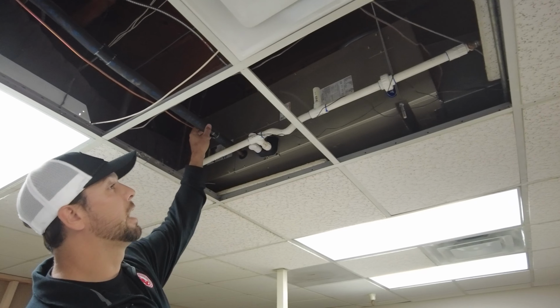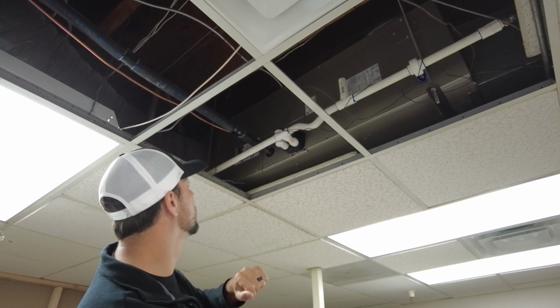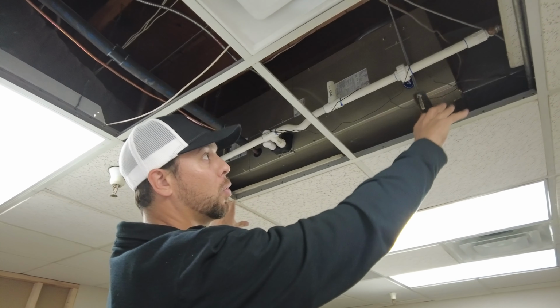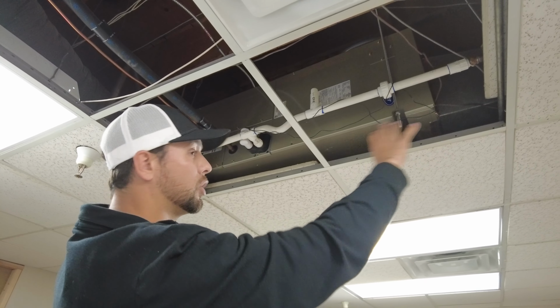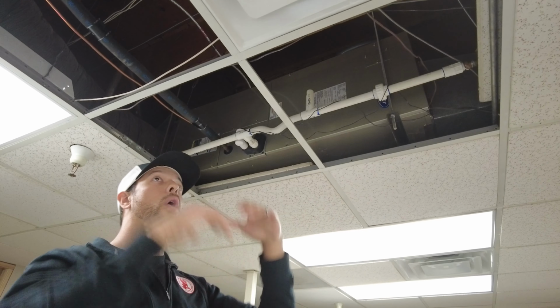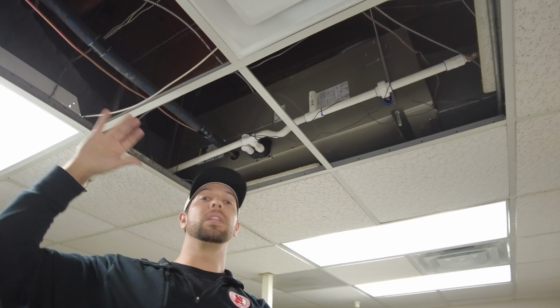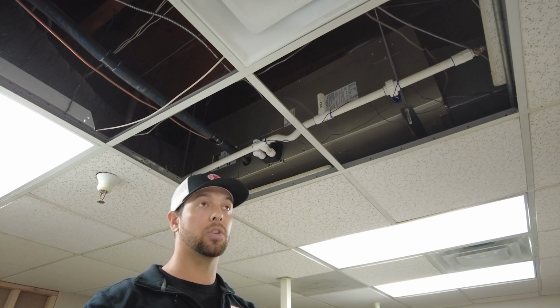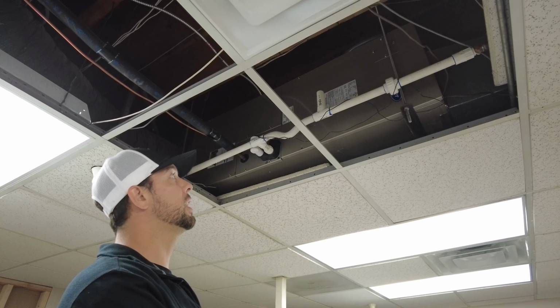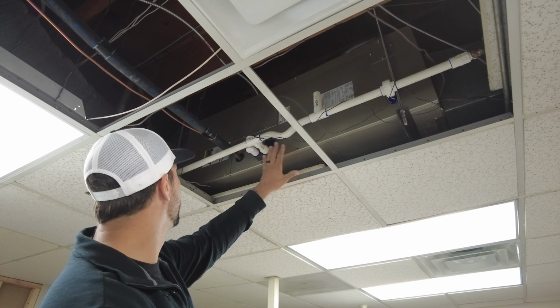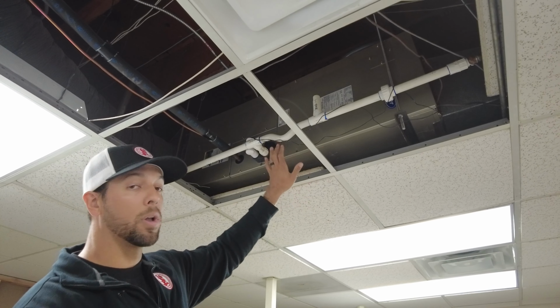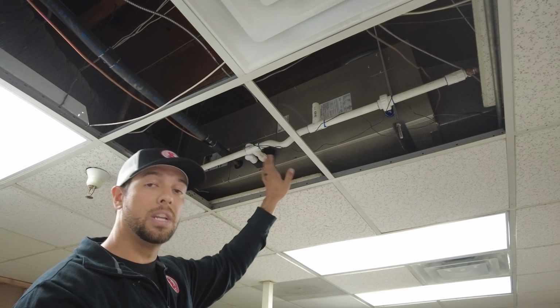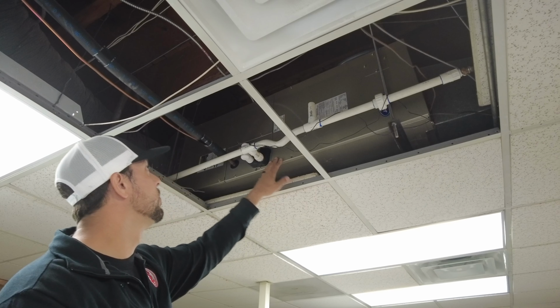We're looking at the insulation on the refrigerant lines — that looks like it's in good shape. Then we're looking for the way the plenums connect, the distribution, and all the ductwork. While we're up here above the T-bar, we can also be looking at the structure and the electrical. There's a lot we can see while we're up here anyway. But right now, just focusing on this unit, we want to make sure we get all the information, the condition, and then document that.